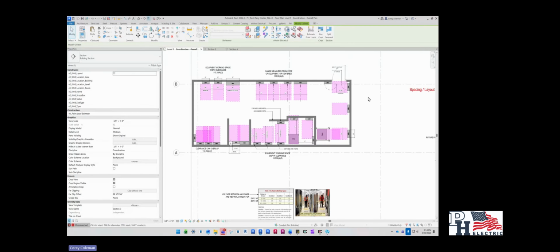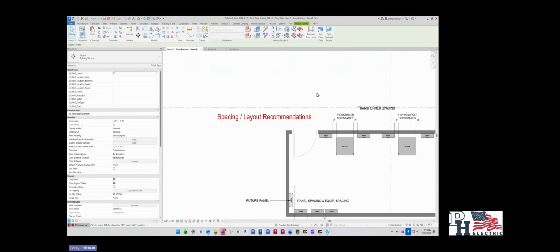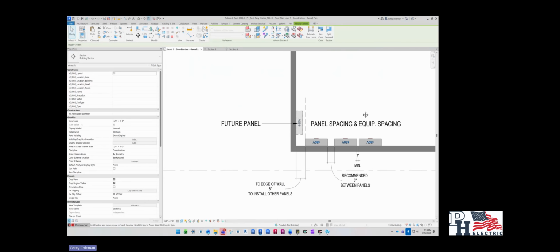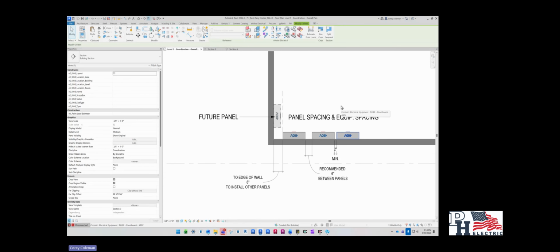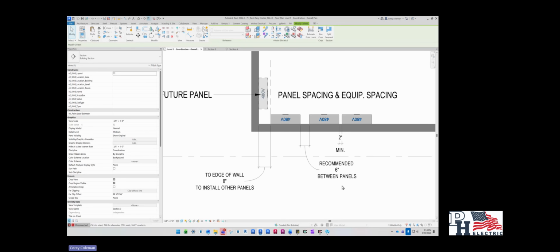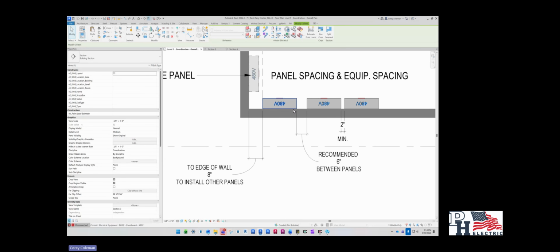Awesome. All right, so let's go over some spacing layout recommendations from all the times that I've been laying out some equipment. So a good rule of thumb is that when you're laying out panels, you should have 6 inches between panels. This is the recommended spacing to give you enough room to run pipes up and down the side of it, give you enough working space with your hands to actually get next to the panel.